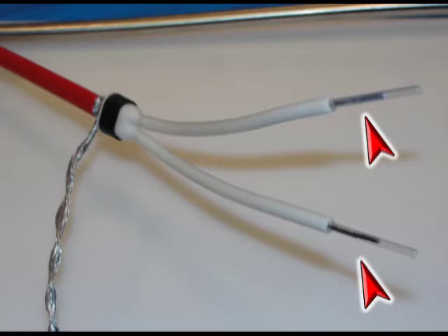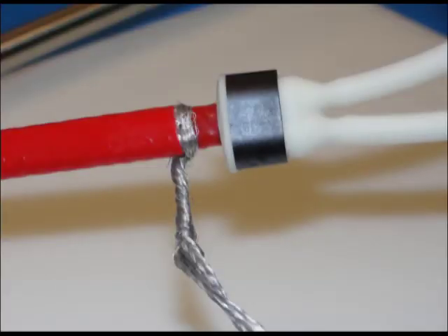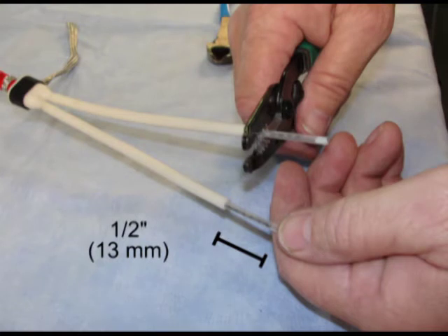If needed, retwist and straighten bus wires. Then insert into the guide tubes as shown. Firmly seat the cold core seal onto the heat tracing. Make sure the bus wires do not kink, bunch or cross over.